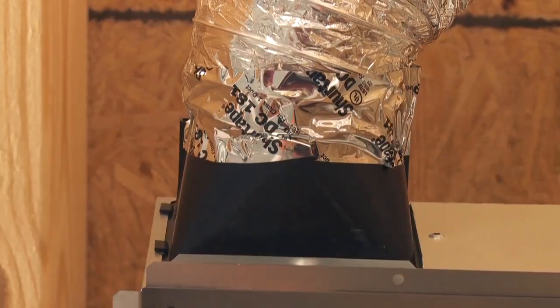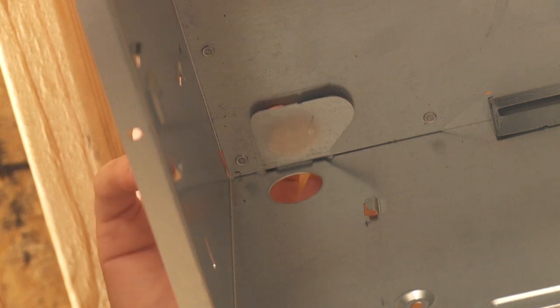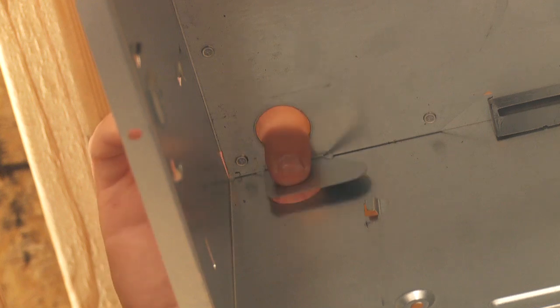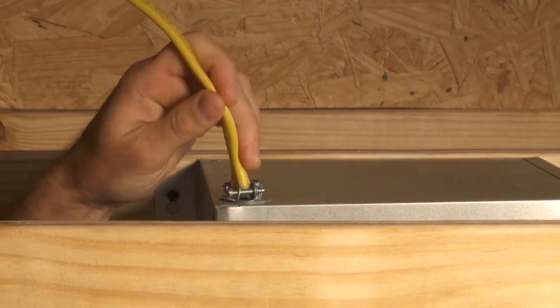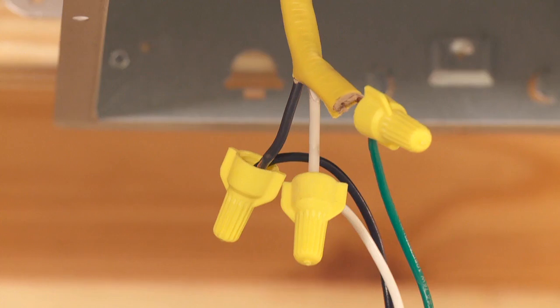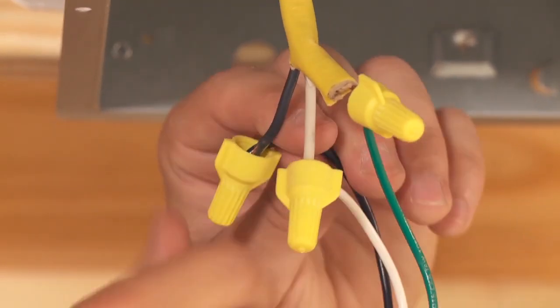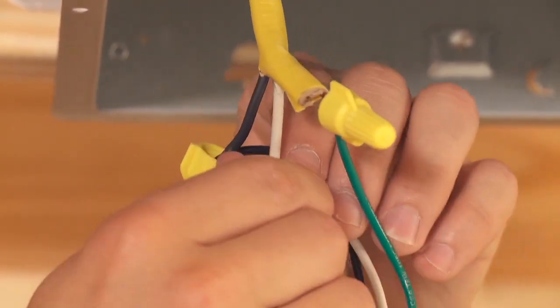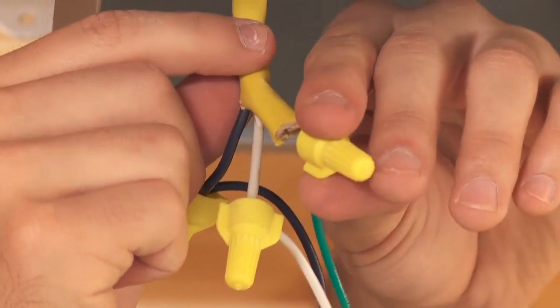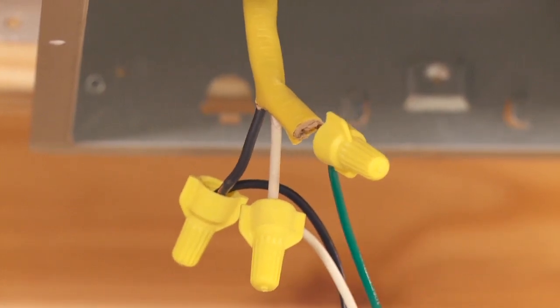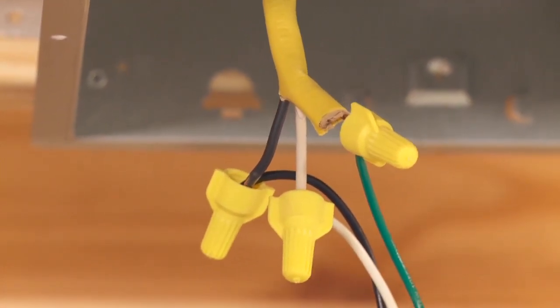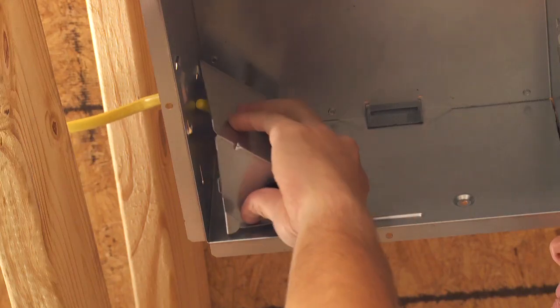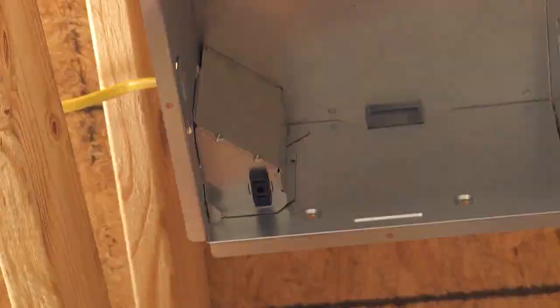Next, you will connect the wiring. Bend the wiring access tab to expose the desired access hole. Run the existing wire into the housing. Connect the power cable to the housing with appropriate UL approved connectors. Connect black to black, white to white, and green to green or bare wire. Reinstall wiring panel and secure with screw provided.